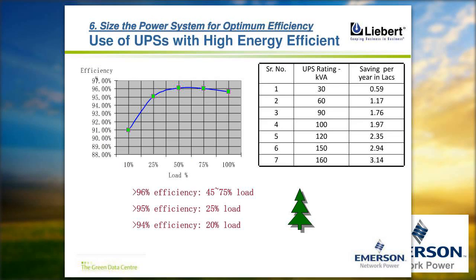Then comes UPS. UPS technology and engineering has also evolved. UPS systems used to give 80-85% efficiency at 100% load, and when you utilized them at lower load, efficiency would be much lower. But today UPS systems are available with 95% plus efficiency across any loading factor. So it is recommended that you take high efficiency UPS systems of around 95% plus, and that 95% efficiency should be available irrespective of the utilization percentage.